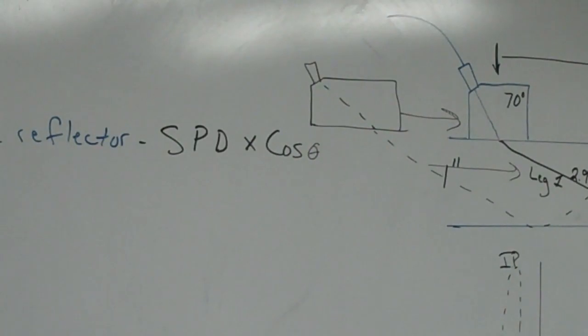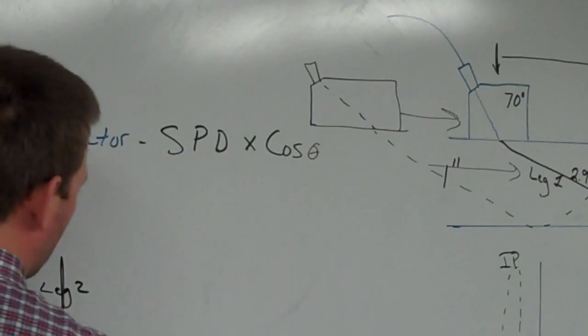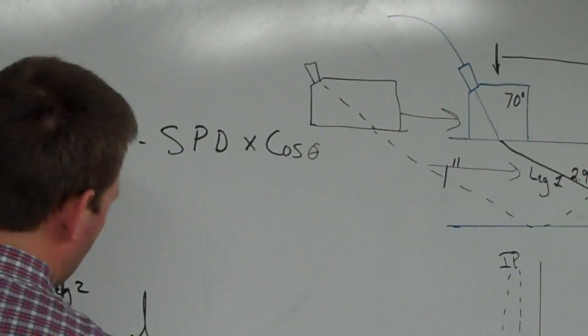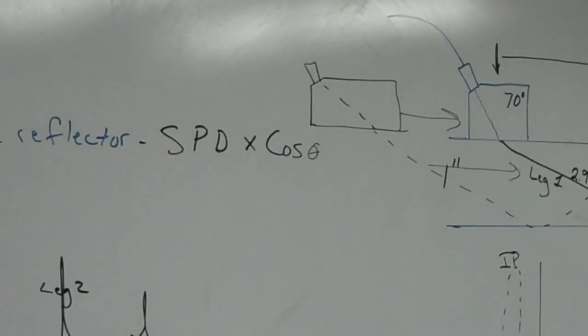If we calculated the V path for that plate over there where we just were, that would be 2 times thickness divided by the cosine of our angle. And the angle in this case was 70 degrees, and you saw that on the transducer over there. So 2 times the thickness of 1 inch divided by the cosine of 70, you should get 5.84 inches. Half of that, which is one leg, would be the thickness divided by the cosine. So 1 divided by the cosine of 70, that's where we got our 2.92. That's one leg each. So one leg travels down, one leg travels back.